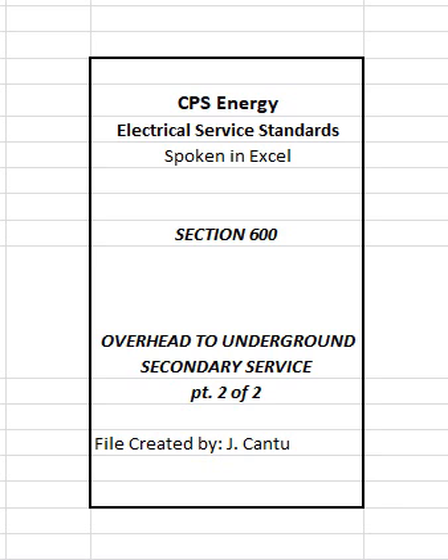606 Service entrance conductors. Customer is responsible for furnishing and installing all service entrance conductors on the load side of the POD as outlined in Article 605(3). 606(1) Size. Service entrance conductors shall have sufficient ampacity to carry the load as determined by the NEC and other applicable codes, and in no case be smaller than number 8 AWG copper or number 6 AWG aluminum. Service entrance conductor sizes shall not exceed those specified by CPS Energy for meter sockets or other CPS Energy metering equipment, refer to Section 1800.